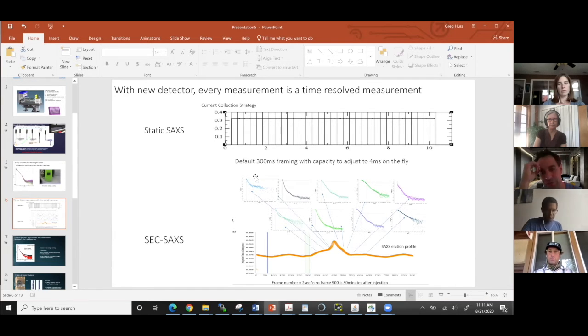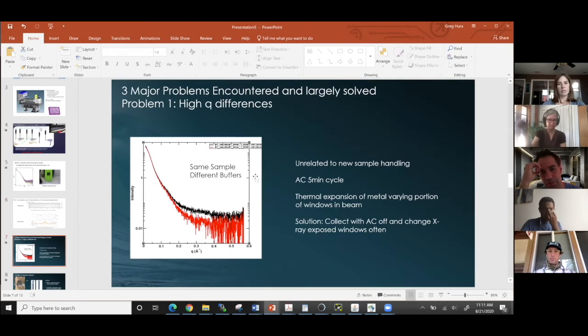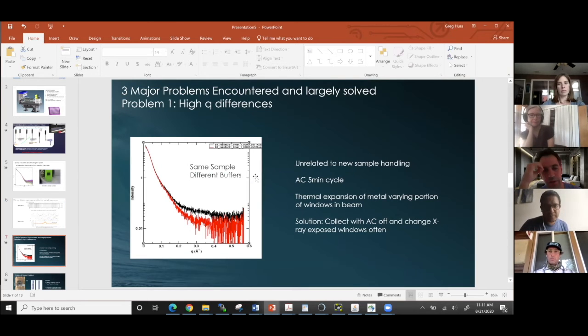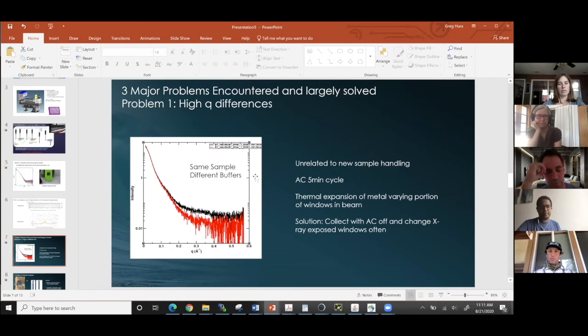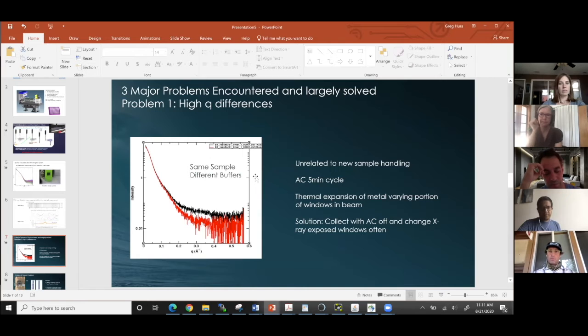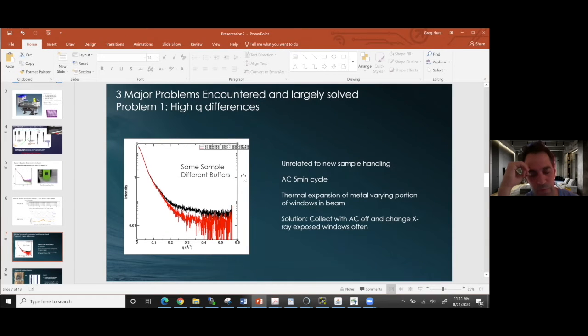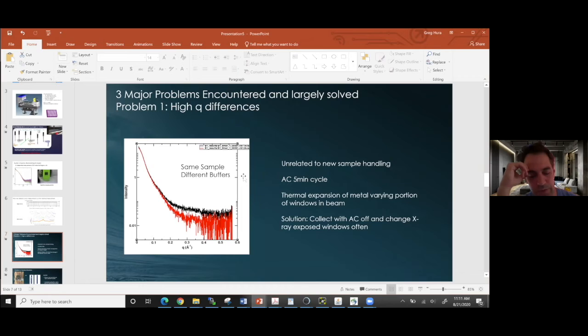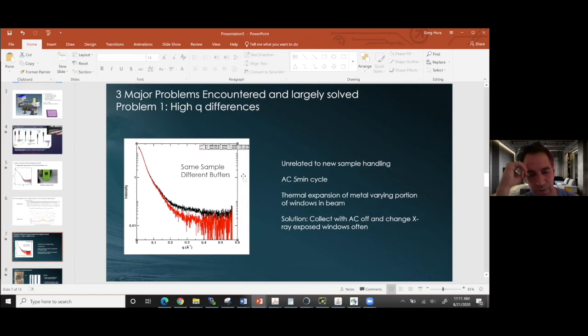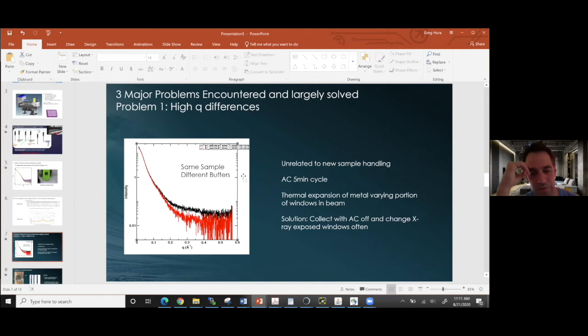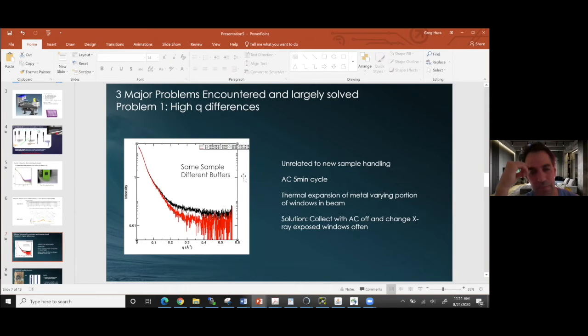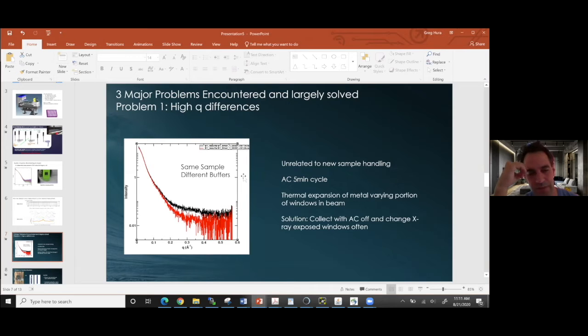There have been issues with this new system that we're still working on and improvements to be made. We usually ask you to send us a buffer before your samples and a buffer after your samples, and we can subtract either from that same sample and get a scattering profile and compare the two and make sure they agree. And sometimes that doesn't agree. So I'm going to show you examples where it doesn't agree on purpose. Hopefully you don't have this. Hopefully you've got mostly things that agree, but occasionally you won't.